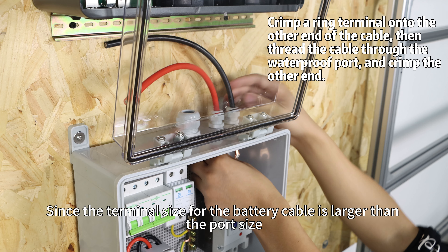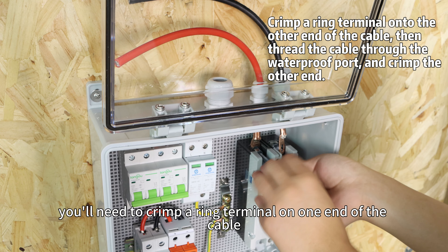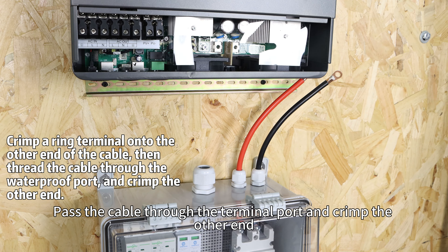Now let's begin with the battery connections. Since the terminal size for the battery cable is larger than the port size, you will need to crimp a ring terminal on one end of the cable. Pass the cable through the terminal port and crimp the other end. Then connect the circuit breakers to the inverter and the battery bank. With this, we have completed the battery circuit connections.